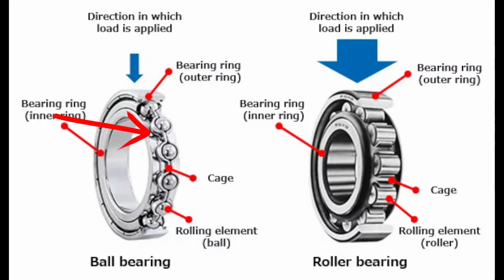They handle axial loads far better than a roller does. Rollers are really good for your radial loads, your up and down, but they don't take axial loads in and out very well. Ball bearings can't handle as much weight, but they handle axial and radial loads really well, which is why the majority of the motors we use are going to be a ball bearing style. So we have our race here. We have our inner race, outer race. We have our balls in there with our shields.